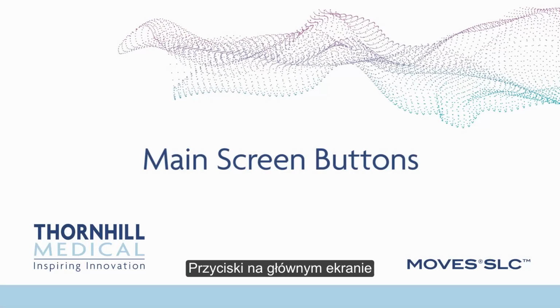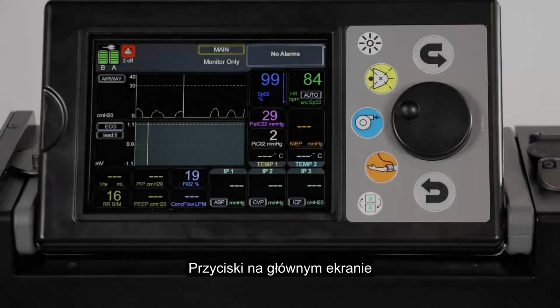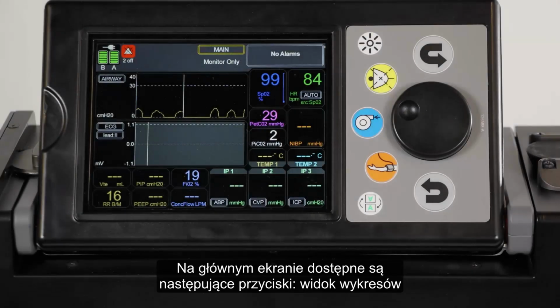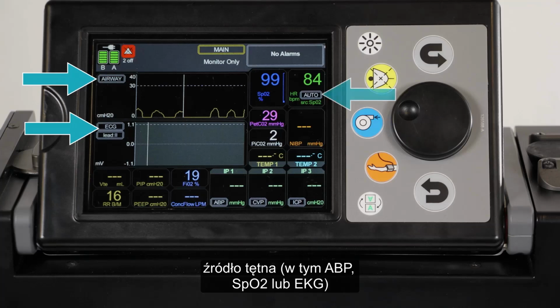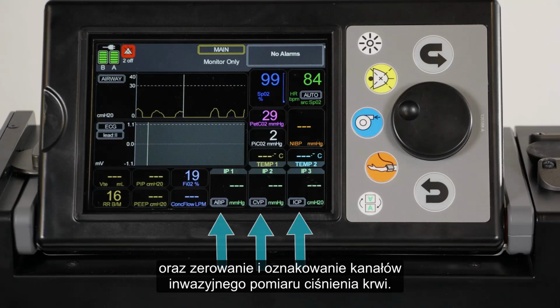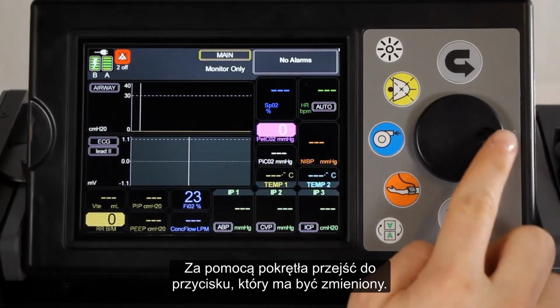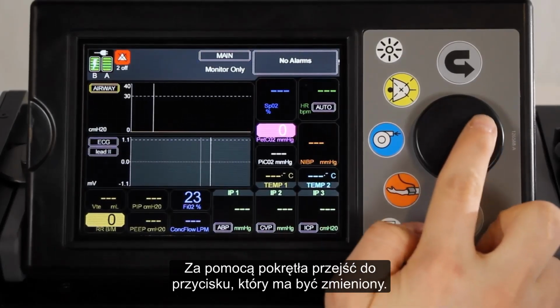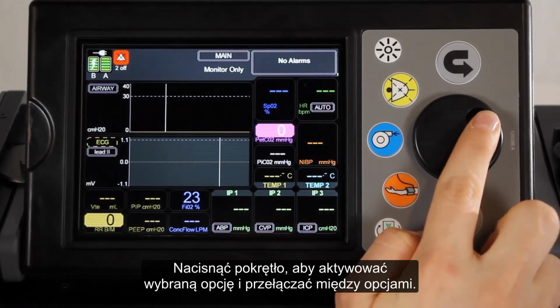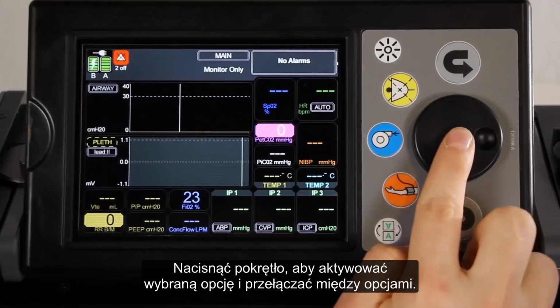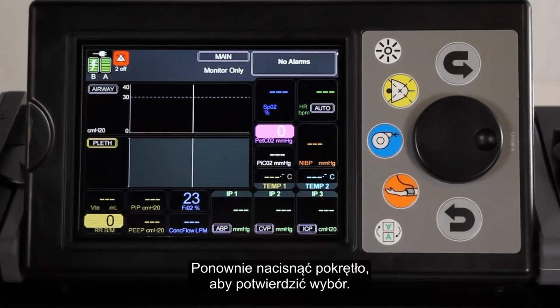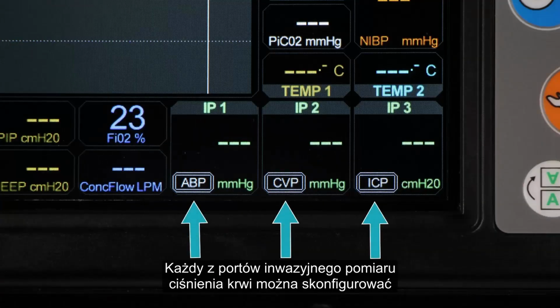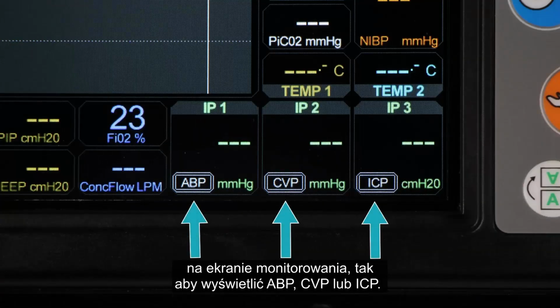Main screen buttons. The available buttons on the main screen are the chart view, the source of heart rate including ABP, SpO2, or ECG, and zeroing and labeling the invasive blood pressure channels. Use the jog wheel to navigate to the button you would like to change. Press the jog wheel to activate the selection and cycle through the options. Press the jog wheel again to confirm. Each of the invasive blood pressure ports can be configured on the monitor screen to display ABP, CVP, or ICP.